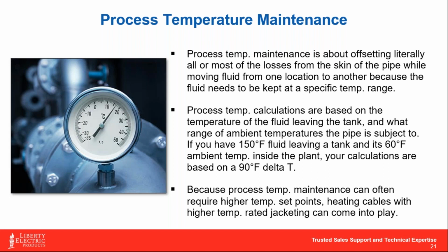Remember, I told you early on in this presentation that the intent of the cable is not to heat what is inside of the pipe. And the only time that that actually can happen in most cases is if the heat trace system is still running and the fluid inside of your pipe stops.